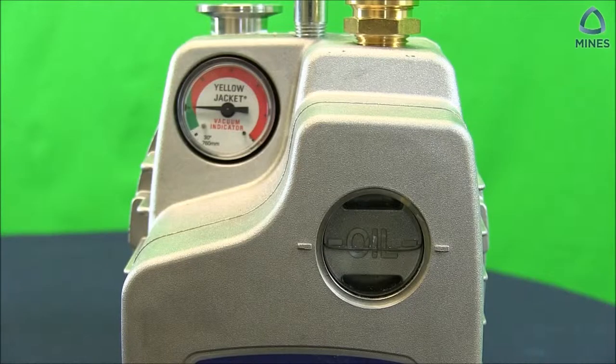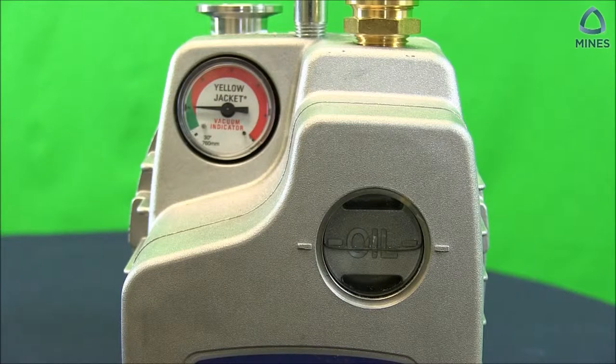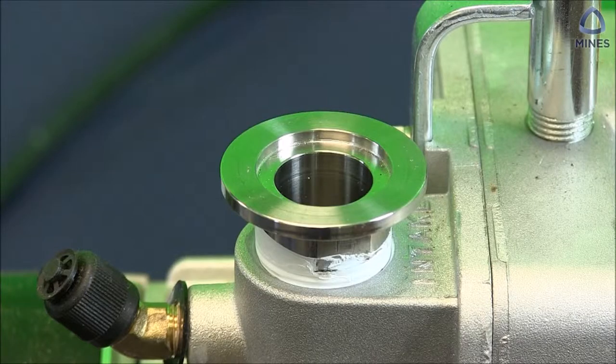Recall in the previous videos, we have confirmed that all the necessary components of the kit are present. The pump is filled with pump oil or fluid, and the pump has been tested for proper operation. We have also replaced the as-received flare fitting on the pump with an NW25 flange needed to attach the aluminum base plate assembly.